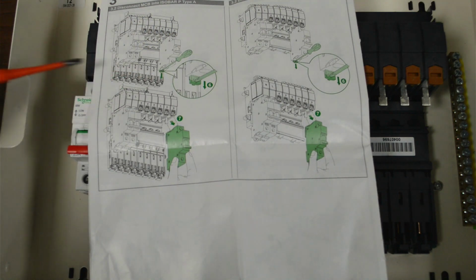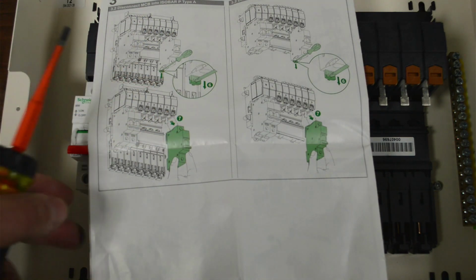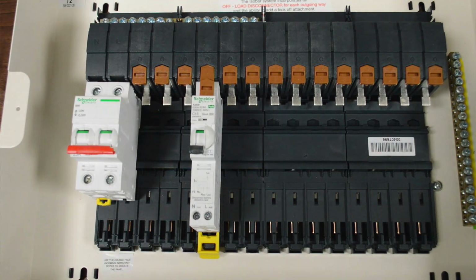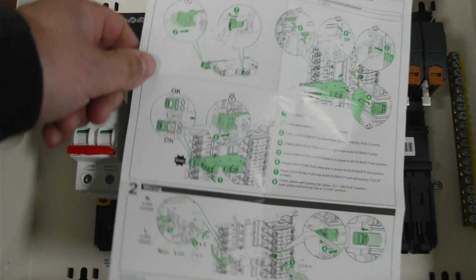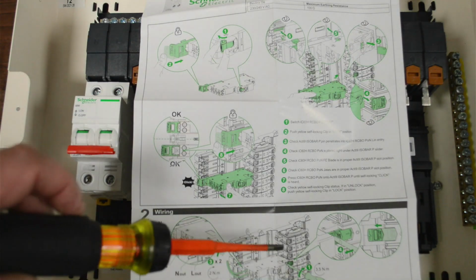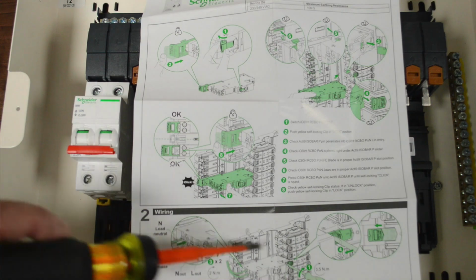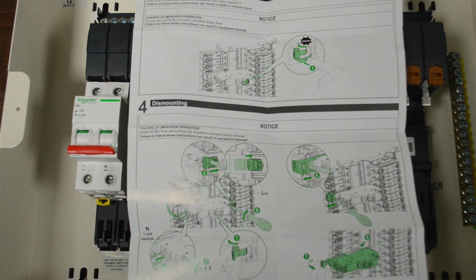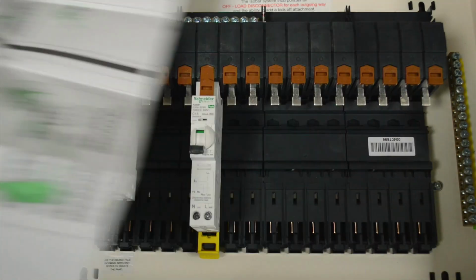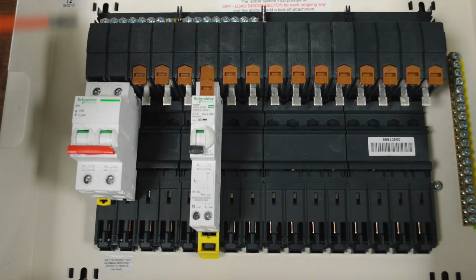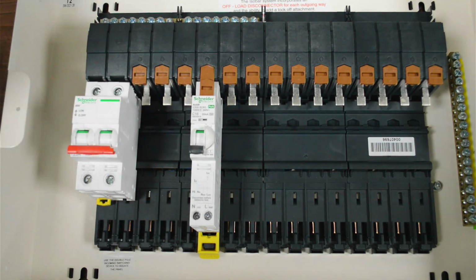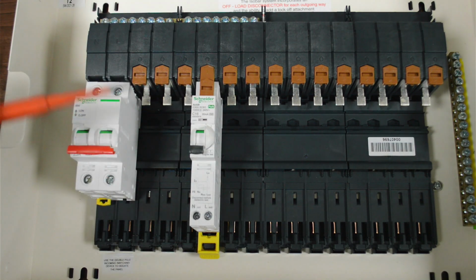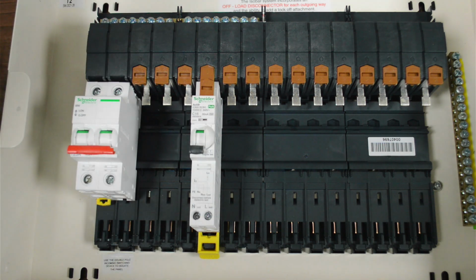That gives you a bit of a typical layout of how you might go along on the layout inside the enclosure itself. So I thought that was interesting, and again, this is for the RCBO. Basically just running through the locking in and out process, the torque values, so you can see it's 3.5 Newton meters on that particular terminal. It's interesting stuff. Hope you found that useful, just having a little look through this Schneider Isobar P board and actually physically putting in an RCBO and then being able to remove it, and some of the safety features and benefits of this particular product.